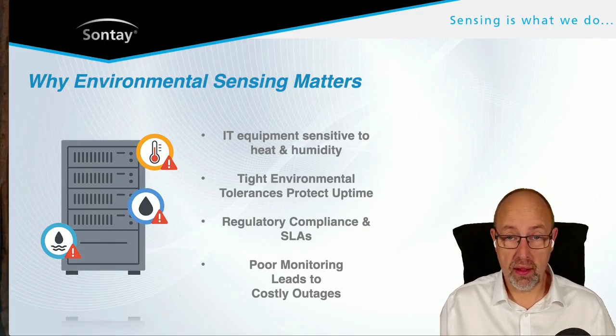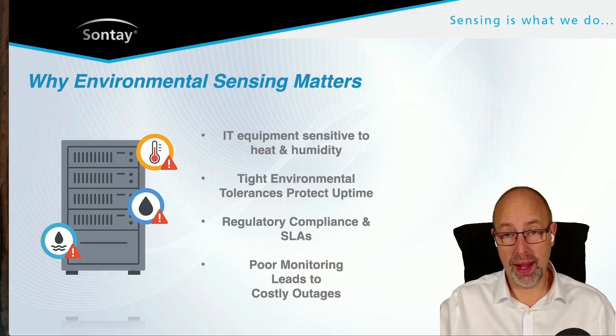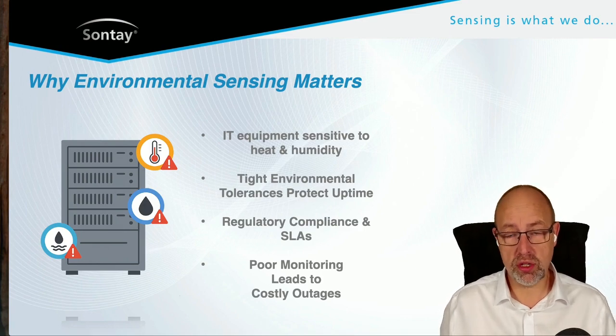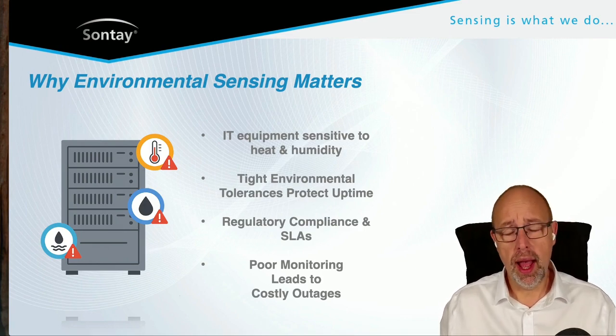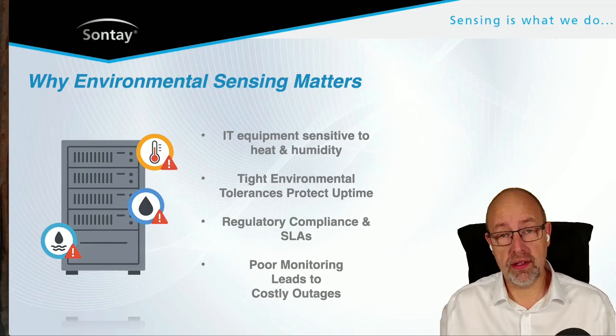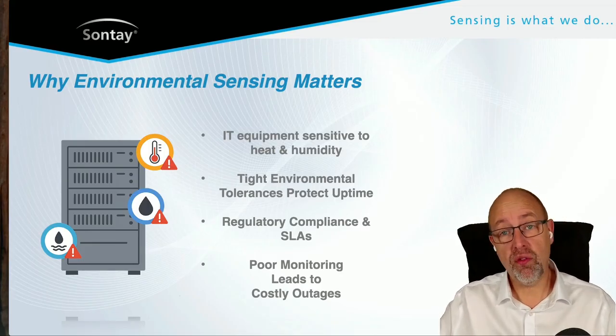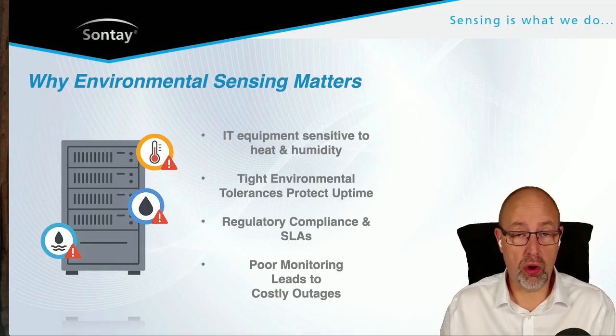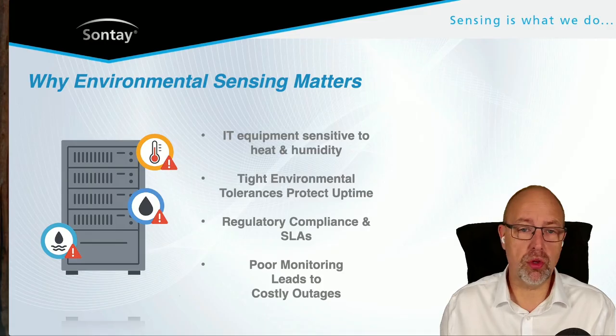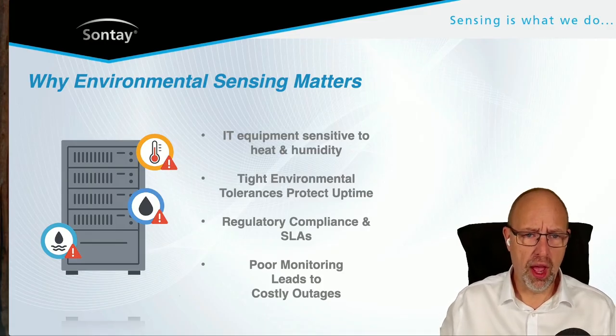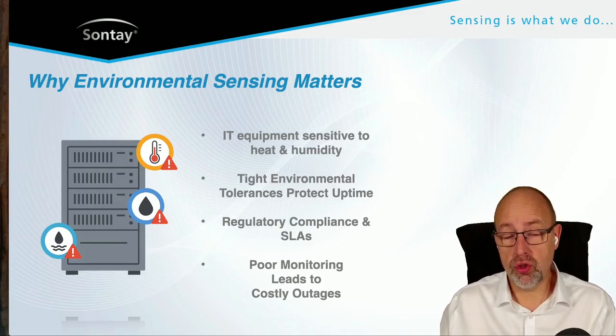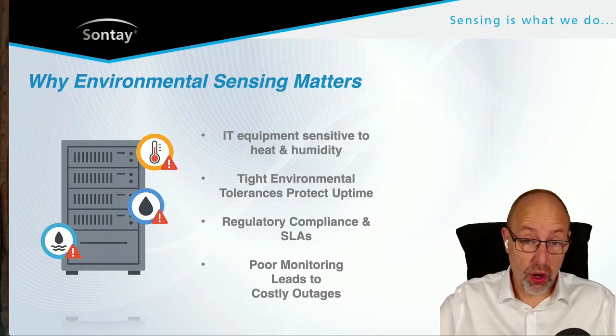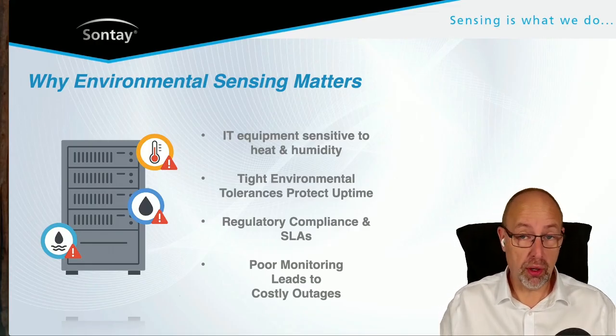So we have valves which open to allow more or less cooling into a space. The flow of water around the system will dictate how fast or slow the pumps are operating in a modern system with two-port valves. There's a lot of monitoring and control that goes into a data center, and the redundancy applies to all of that.